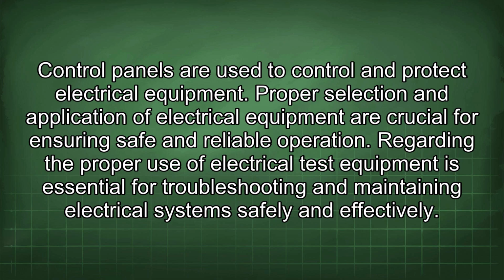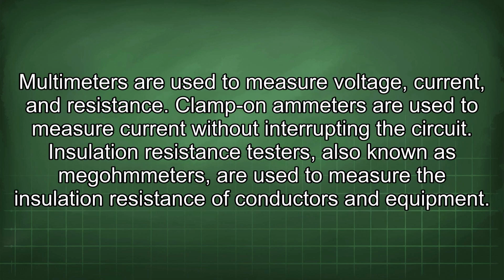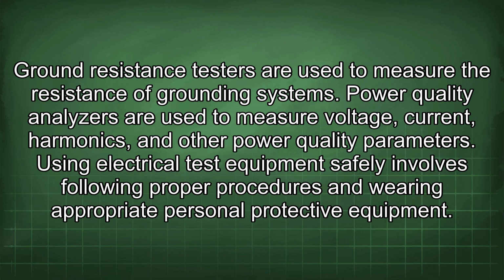The proper use of electrical test equipment is essential for troubleshooting and maintaining electrical systems safely and effectively. Multimeters are used to measure voltage, current, and resistance. Clamp-on ammeters are used to measure current without interrupting the circuit. Insulation resistance testers, also known as megohmmeters, are used to measure the insulation resistance of conductors and equipment. Ground resistance testers are used to measure the resistance of grounding systems. Power quality analyzers are used to measure voltage, current, harmonics, and other power quality parameters.